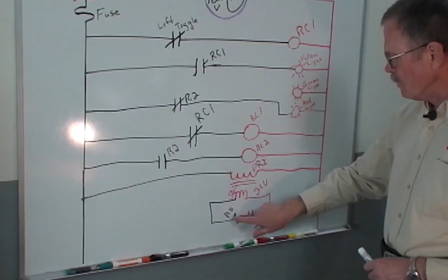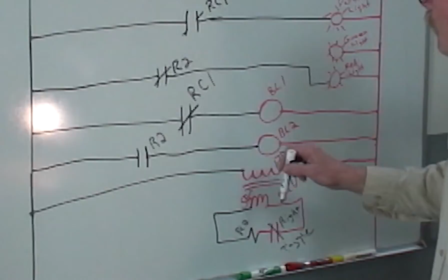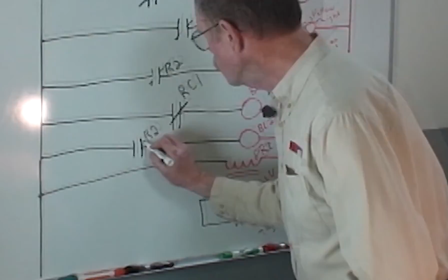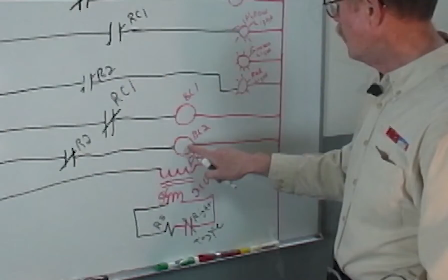What's going to happen next? What else do I have to do? I've got another toggle in the 24-volt circuit. When I close the right toggle, R2 is going to energize this 24-volt coil, which will open the normally closed set of points and close the normally open set of points. That means the red light is going to go off, and big light number 2 is going to turn on. Red light went off, big light number 2 went on.